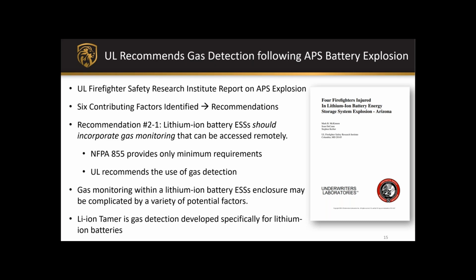Tom and Nick will get into that a bit more, but their second recommendation was really around gas detection: that energy storage systems should incorporate gas monitoring that can be accessed remotely. They point out that NFPA 855 provides only the minimum requirements for an energy storage system, and that even if the energy storage system at the site was installed today, it would not be required by code to have gas detection installed.